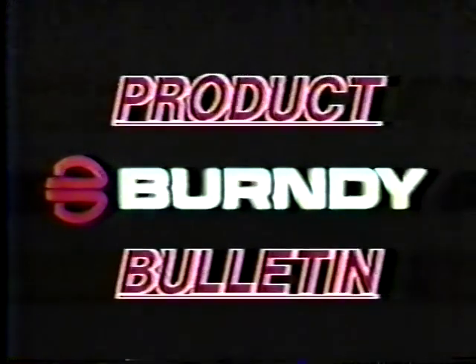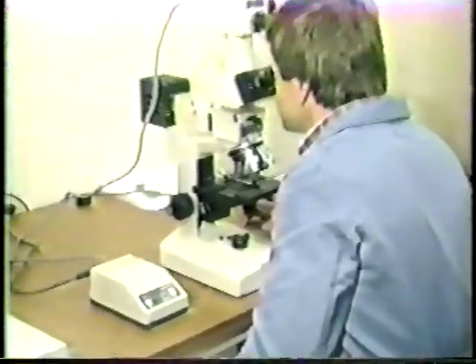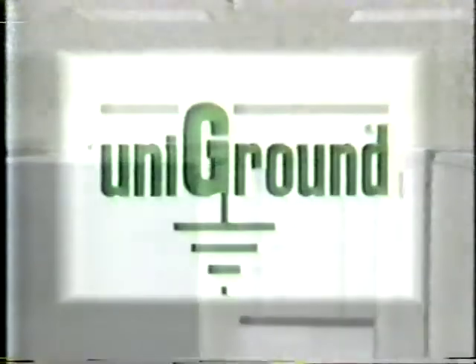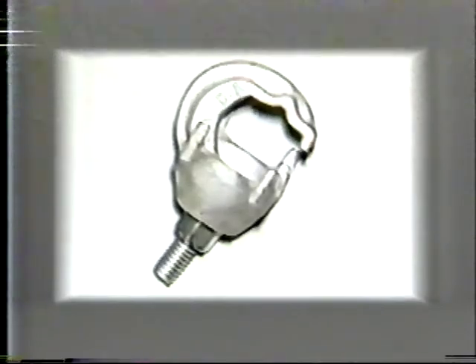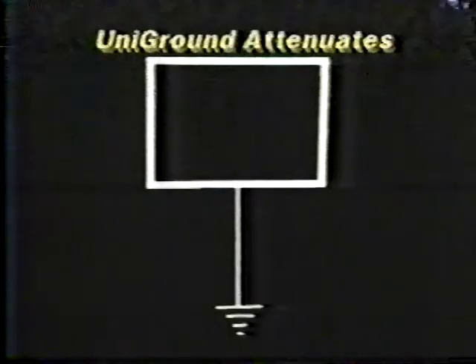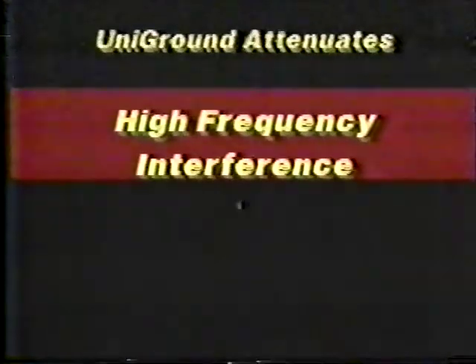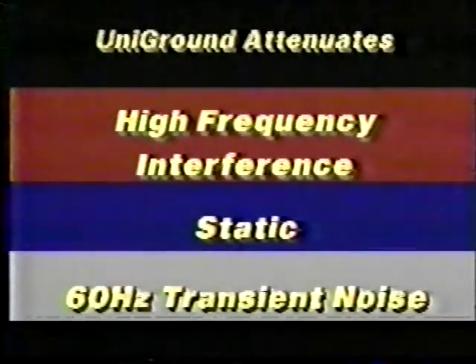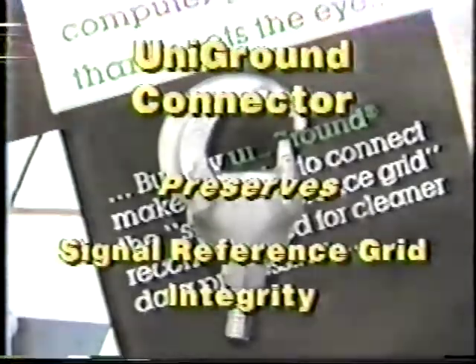Burndy, the leader in electrical connector design, is continually developing new products to meet the ever-changing needs of the electrical industry. Recognizing that electrical codes do not fully address the noise requirements of today's computers, Burndy introduces the Uniground connector. This unique connector provides a low-impedance ground path to effectively attenuate high-frequency interference, static, and 60 Hz transient noise. The Uniground connector preserves the signal reference grid integrity specified by leading computer manufacturers.